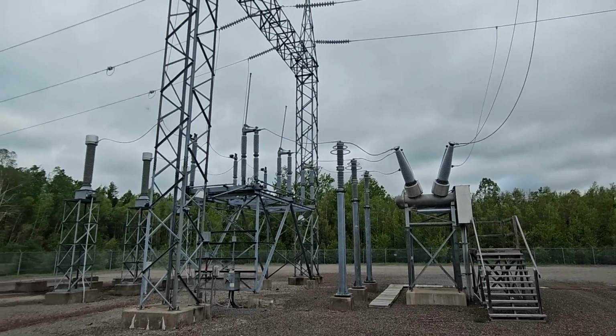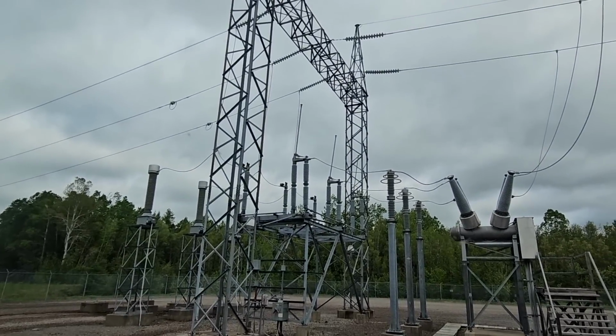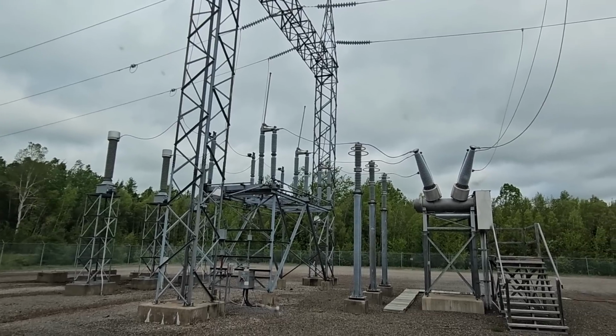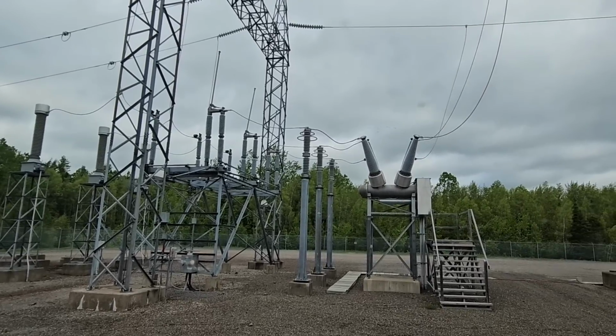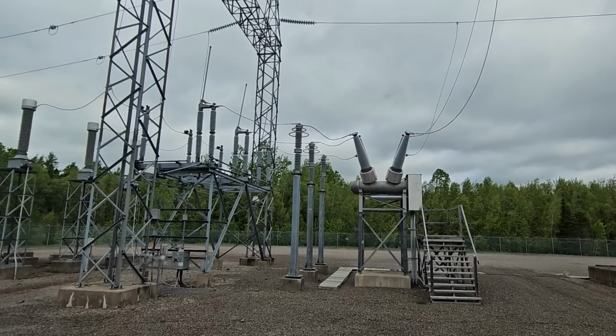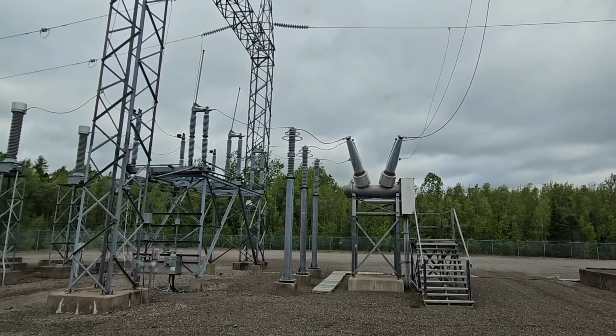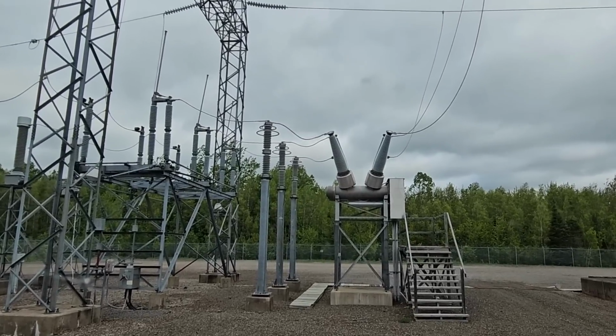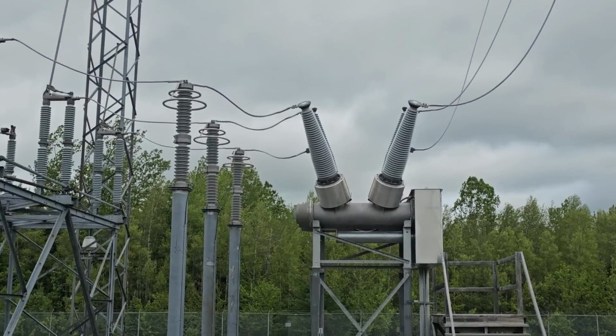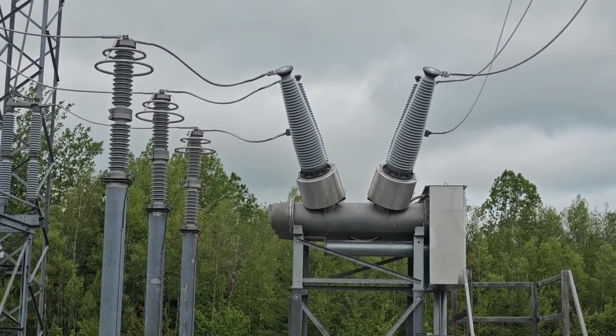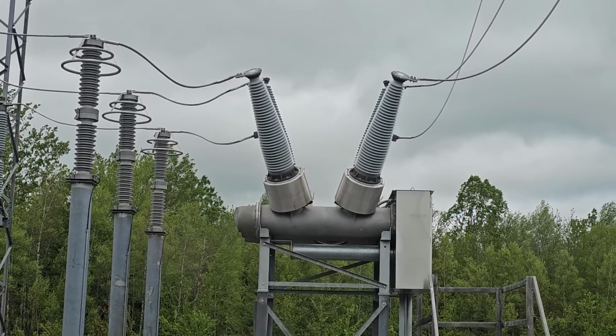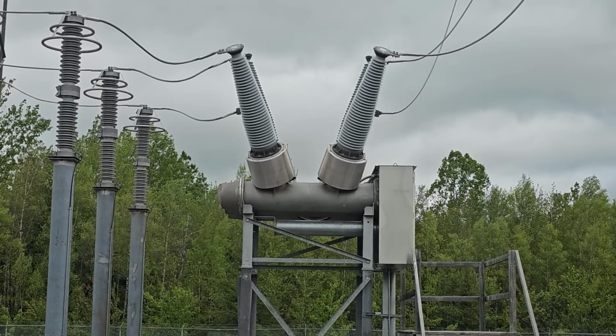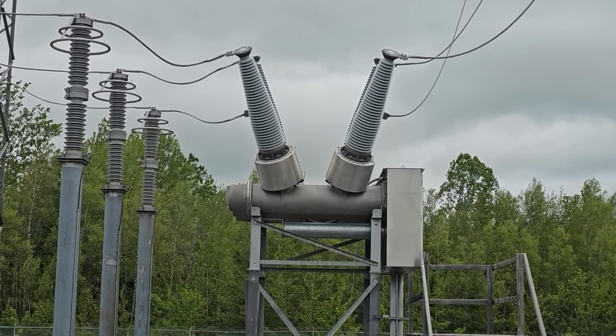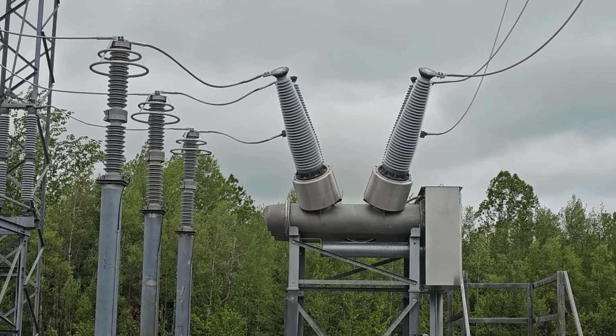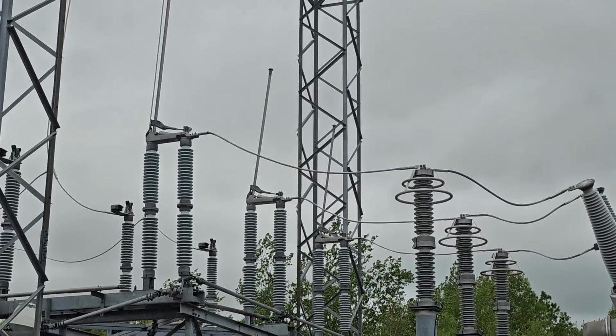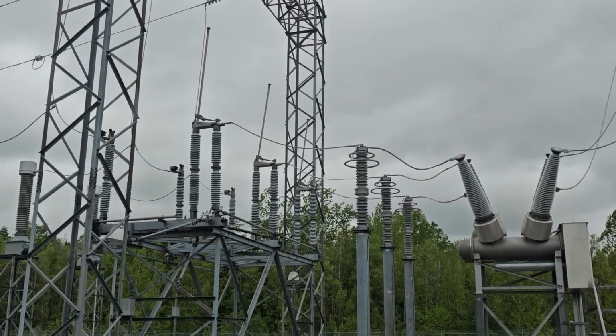So because the guys are working on the line off to the left of the screen, we had to open the line. That was done remotely through this breaker. In a lot of my videos, when you see me operating reclosers and stuff, that's all stick operated or handles or push button in the terminal. These air breakers can be operated within the terminal switchgear, but they're typically operated remotely right from our head office. So this guy here, that gets disconnected internally, and it's done in such a way that it breaks the arc. You can't just go and open a switch like this while there's load on it, or you're gonna burn the place down. It would be really bad.